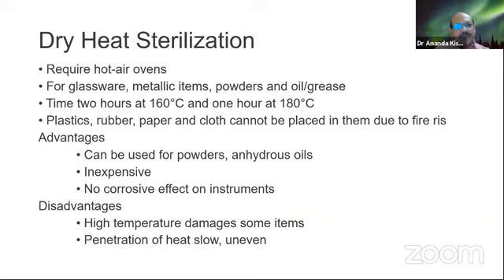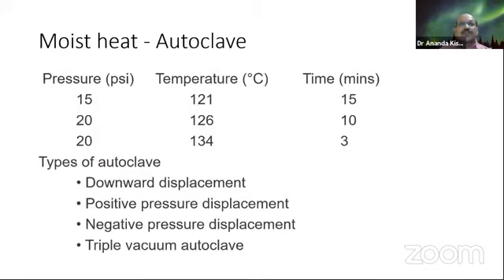Intentionally, I'm skipping this slide because basic orthopedic instruments should not be sterilized by dry heat. Basically, we have to use the autoclave, that is moist heat. There are three ways of autoclaving. Standard autoclaving requires 15 pounds per square inch pressure, a temperature of 121 degrees centigrade, and the time is 15 minutes.